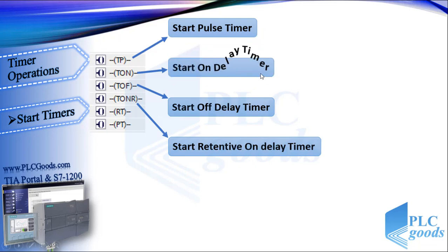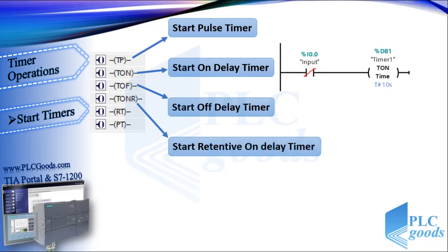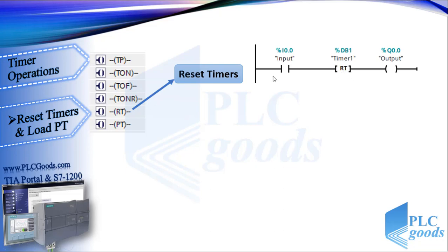For example, suppose we've inserted an on-delay timer. With this program I can start timer 1 from another network with a preset time of 10 seconds. Also this is its FBD symbol. Here are reset and load preset instructions. The reset instruction is used to reset timers — like this program, which can reset timer 1 with the I0.0 address. Note that both sides of this instruction have the same RLO, so if the I0.0 address is activated, timer 1 is reset and also Q0.0 will be on.